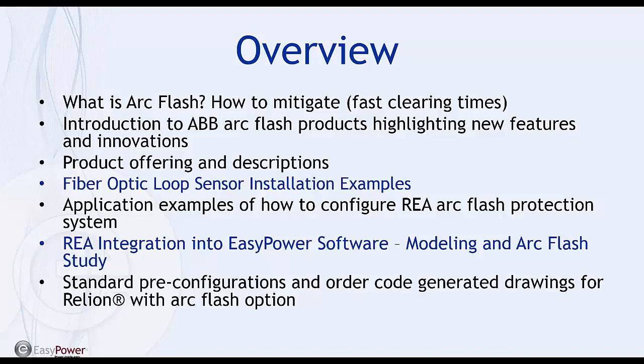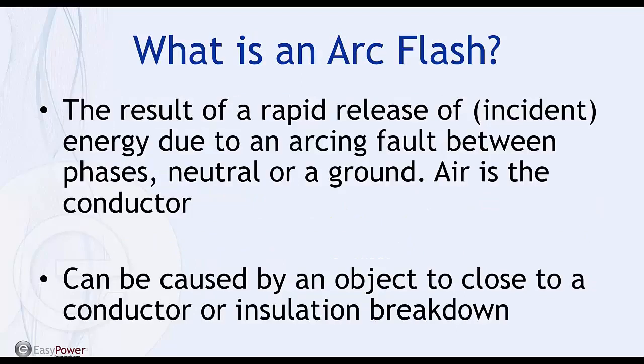So let's start. What is an Arc Flash? It's the rapid release of incident energy due to an arcing fault, across the conductor. The way we measure it is incident energy, and it's caused by an object being too close to a conductor or an insulation breakdown. So that's a basic idea of what Arc Flash is, and it's something that's very, very serious. It happens often enough, and at every company I've ever worked at, there have been injuries and fatalities, and statistically it's occurring much more often than it should. So that's where we start.